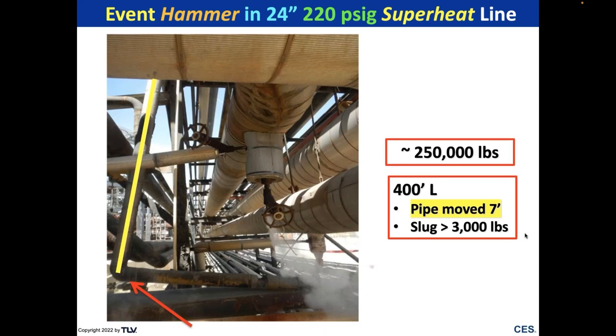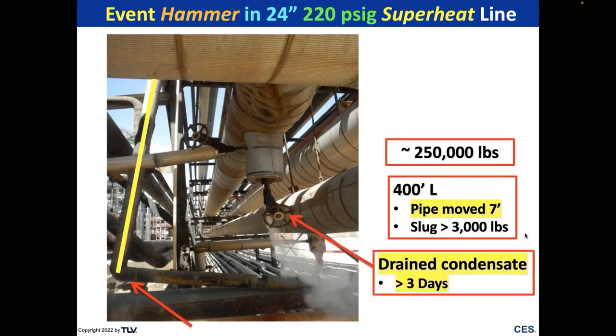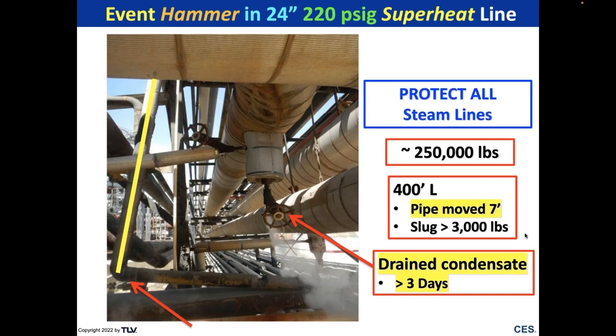They thought it was superheated and had no condensate, but when they opened various drain valves, it drained condensate for three days. When you've got superheated steam, the high-temperature steam moves over the water, and if the water doesn't have a drain point — it's like the sun trying to evaporate all the water in a lake; it won't get it all. It's not a boiler; it's high-temperature steam moving over water flow. We have to protect all steam lines, including superheated steam lines.